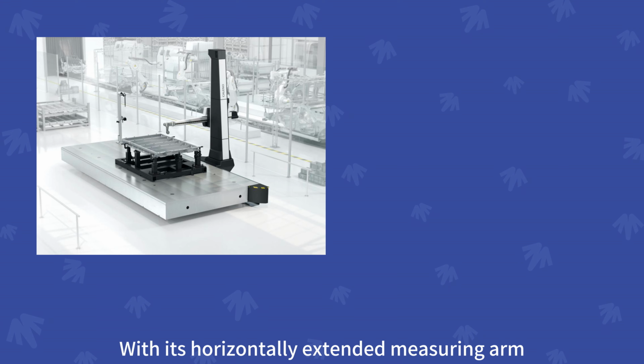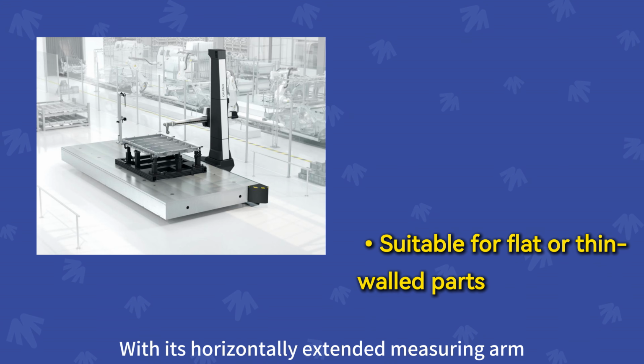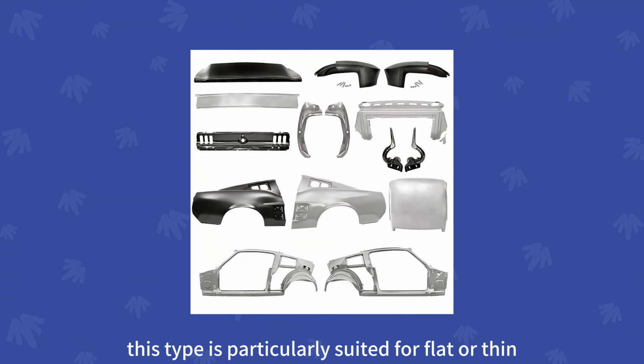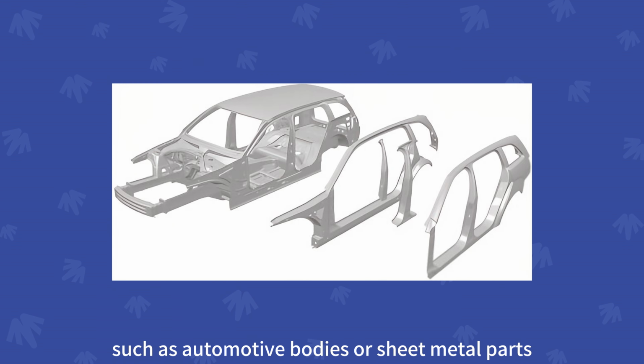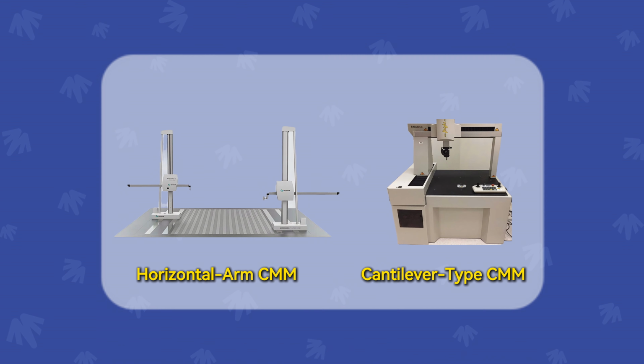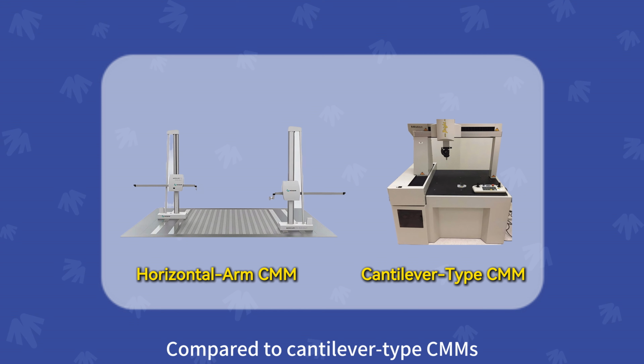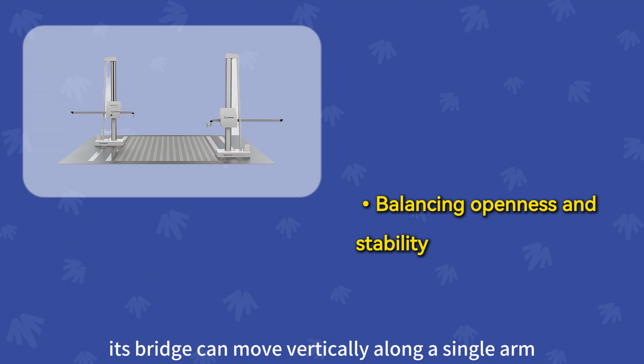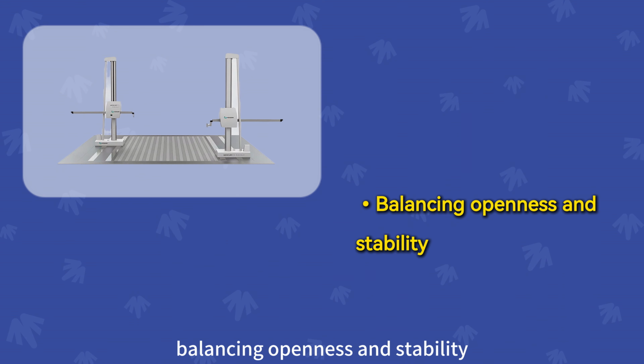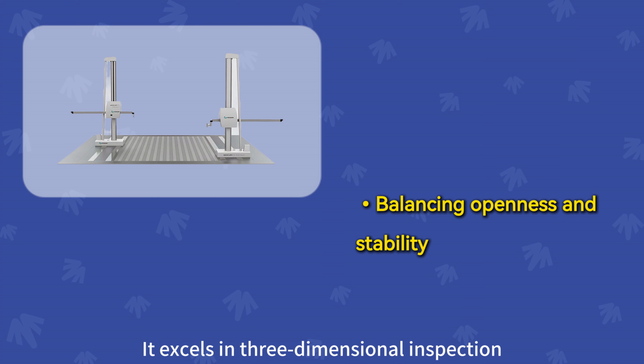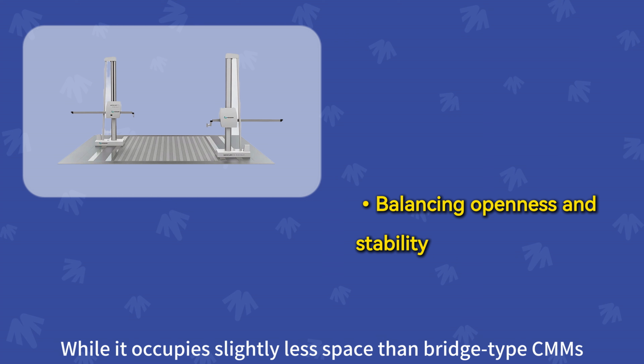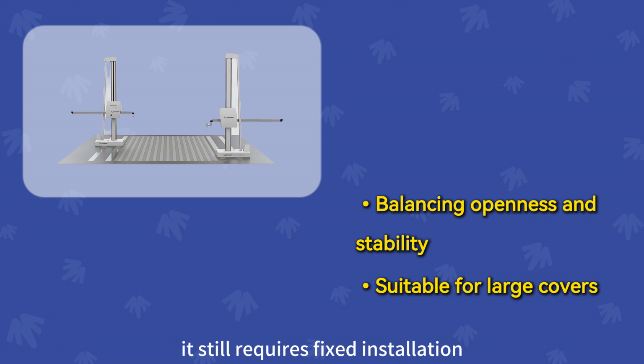Horizontal arm CMM. With its horizontally extended measuring arm, this type is particularly suited for flat or thin-walled workpieces, such as automotive bodies or sheet metal parts. Compared to Cantilever-Type CMMs, its bridge can move vertically along a single arm, balancing openness and stability. It excels in three-dimensional inspection of large components. While it occupies slightly less space than Bridge-Type CMMs, it still requires fixed installation and is not easily movable.